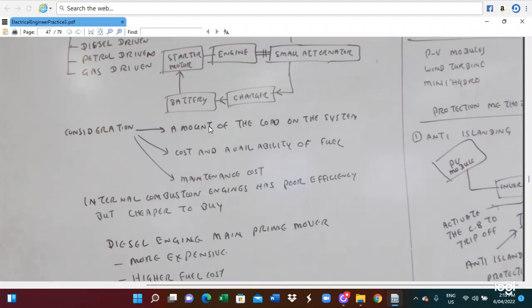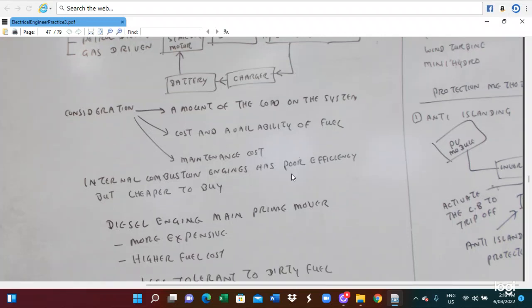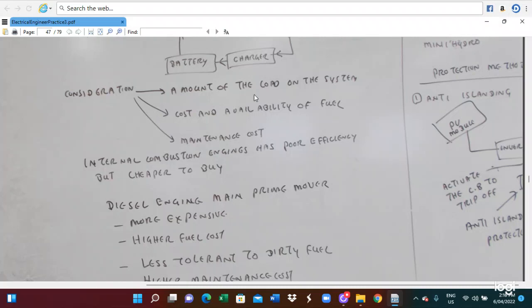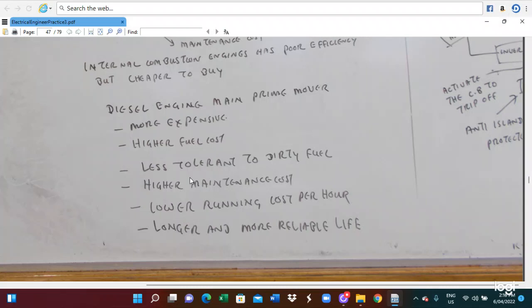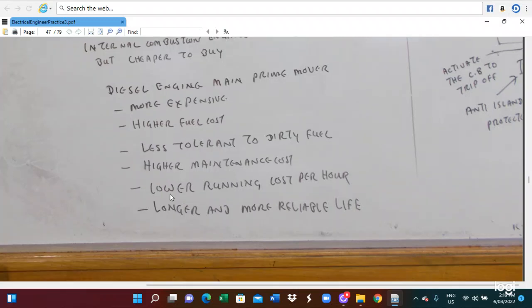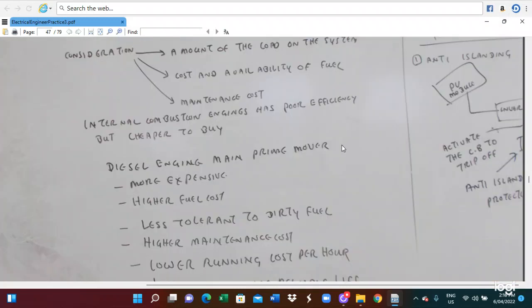In this case, we need to consider the amount of load on the system, the cost and availability of the fuel, and the maintenance cost. Those need to be considered. The internal combustion engine has lower power efficiency, but is cheaper to buy. These engines are utilized as a main prime mover. Diesel engines are more expensive, with higher fuel cost, less tolerance to dirty fuel, and higher maintenance cost, but a lower running cost per hour and a longer, more reliable life. So these are the features of the diesel engine.